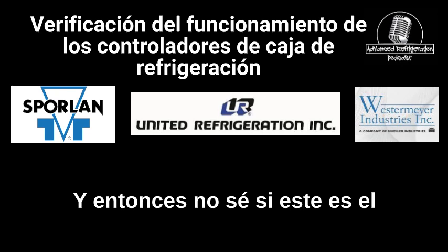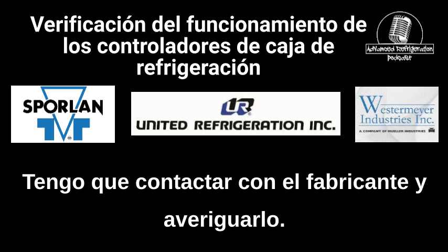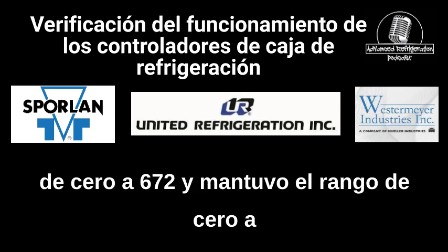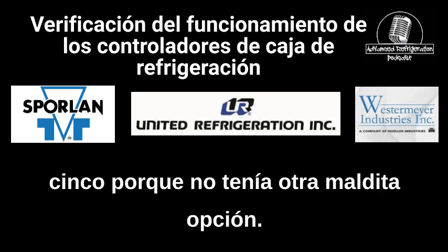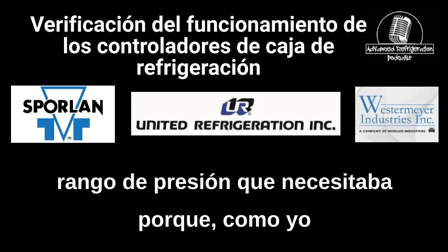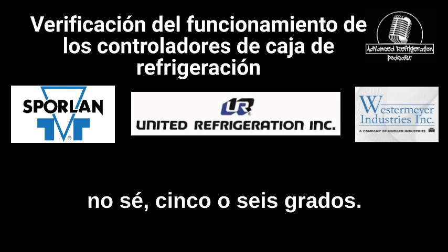And so I don't know if this is the right thing to do, but it worked for now. I've got to contact the manufacturer and figure it out. But I was able to broaden the span, making it read from 0 to 672. And, you know, I kept the range at 0 to 5 because I didn't have any other option. And then I was actually able to achieve the pressure range that I needed. Because, like I said, it was reading off by 20 pounds. With CO2, that's like, I don't know, 5 or 6 degrees.